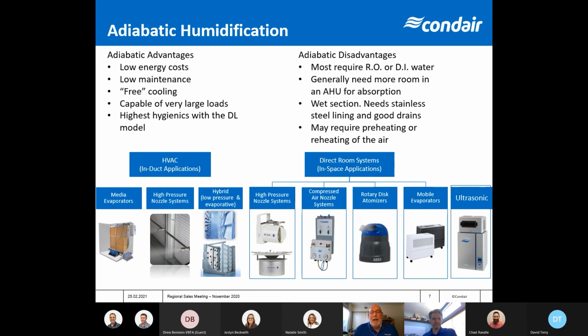Depending on the size of the air handler it goes into, we could have 100 nozzles in there, and we can set it up to turn it down to one nozzle if we want to. So good controllability. It's going to be a wet section, needs to be lined in stainless steel, needs a good drain. The next one here we show, it's our hybrid system.